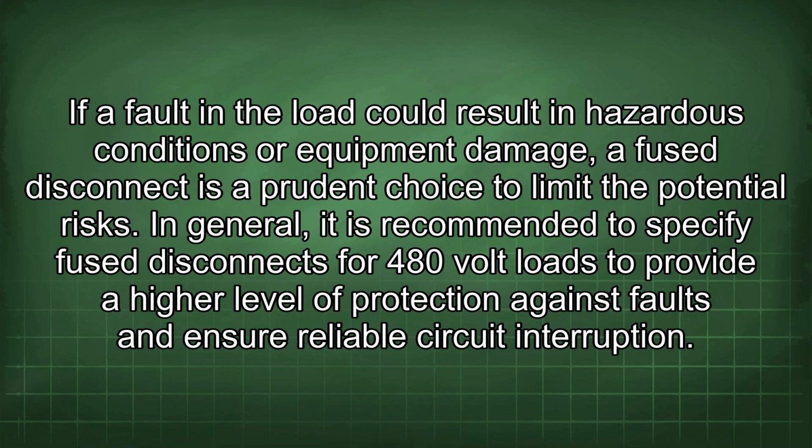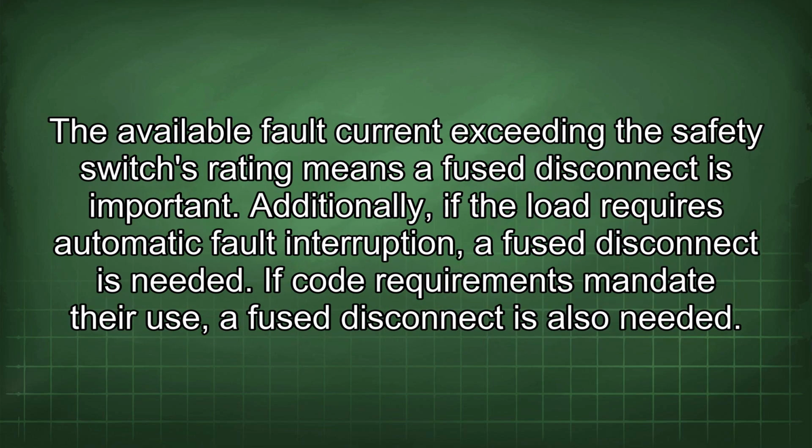In general, it is recommended to specify fused disconnects for 480-volt loads to provide a higher level of protection against faults and ensure reliable circuit interruption. The available fault current exceeding the safety switch's rating means a fused disconnect is important. Additionally, if the load requires automatic fault interruption, a fused disconnect is needed.